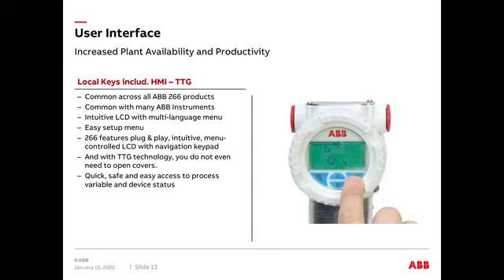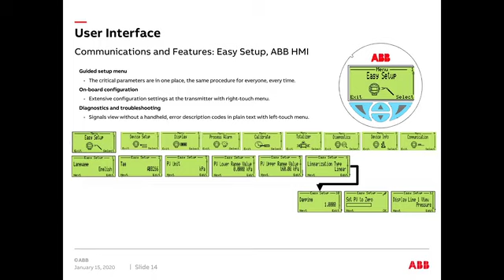When you go into the communication of the easy setup menu, there's the guided setup like I talked about, and configurations you can do. You can set upper and lower level limits. If for some reason you overpressure or have an issue, there's diagnostics you can drill down into. If you're buying an advanced pressure transmitter, you can set up the display, the alarms, and go in and do a calibration, etc.